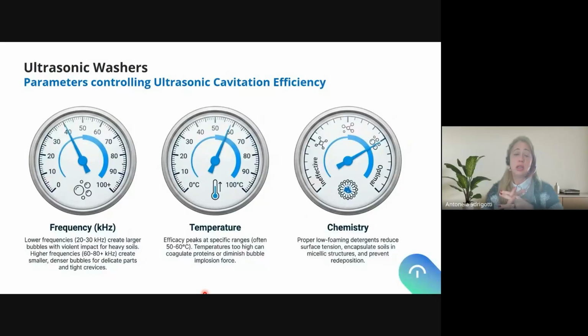The detergent needs to be definitely low foam because the foam will be very detrimental to cavitation energy, because it's a competition between the cavitation or vacuum bubbles and the air bubbles created by the detergent foam. Okay, so low foam, definitely. And we also have to make sure that we use appropriate detergents that the manufacturer states are compatible with ultrasonic processes. Because the same energy delivered to clean instruments and to remove organic residues from the instruments could not be good for the efficiency of the detergent, even more if it's an enzymatic one.